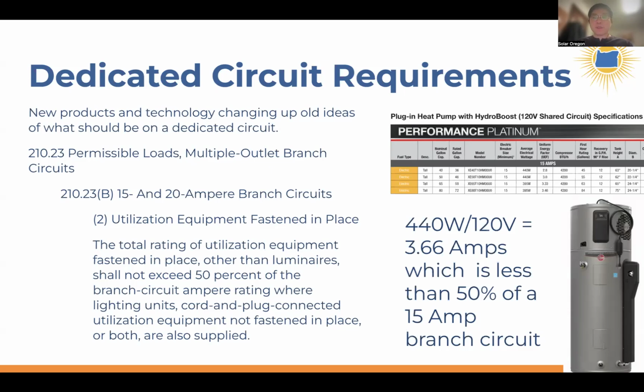There's an electrical code rule saying that if it's a fastened-in-place piece of equipment, which a water heater obviously is, and it's going to be on a branch circuit shared with other items, that fastened-in-place appliance cannot use more than 50% of the amperage rating of that branch circuit.